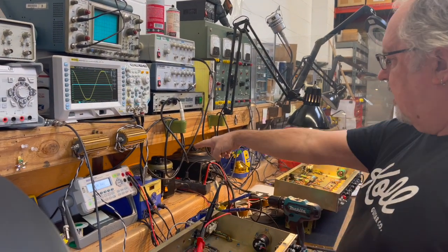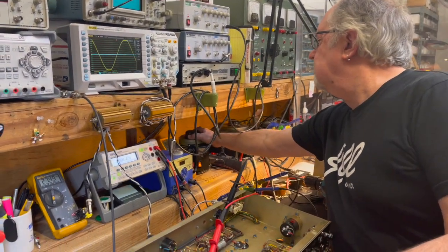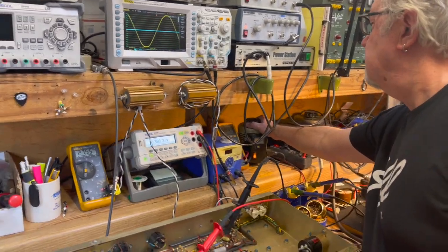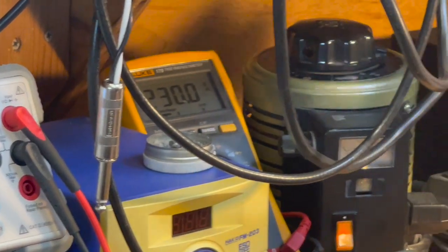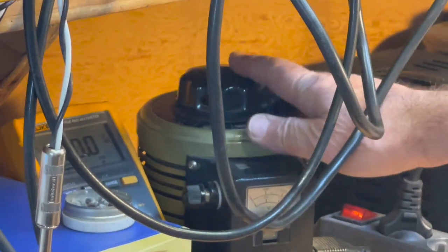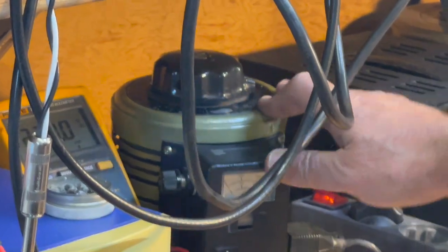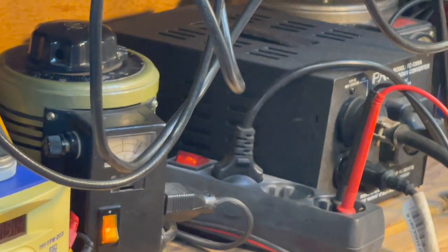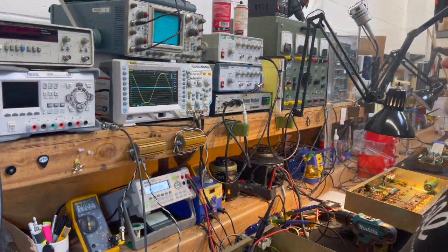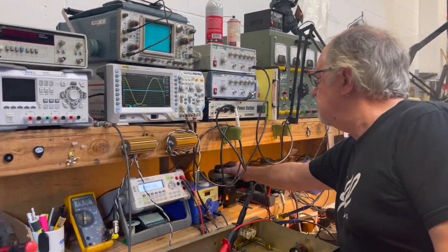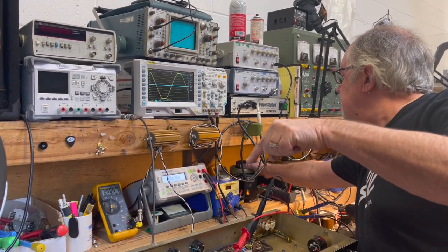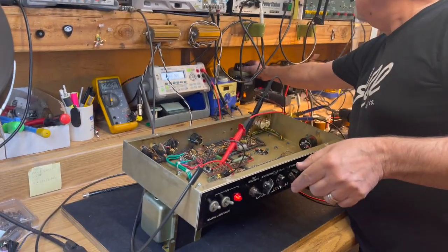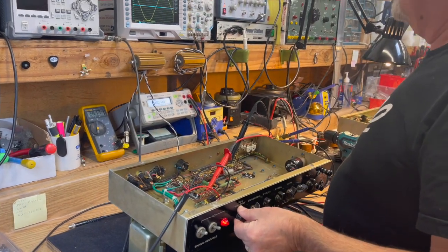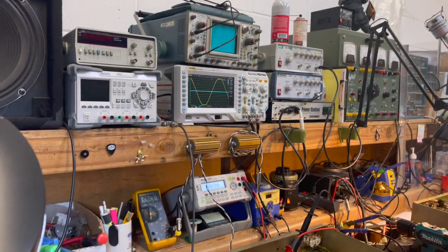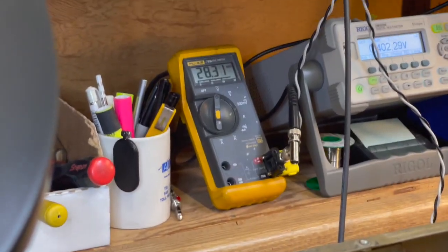We also lost about 3 volts of supply because I've got a step down transformer that I use for European voltage, and a variac here, so there's a little bit of voltage drop across there. So when you start pulling current through it, the voltage drops through all my test equipment. So we compensate for that by jacking the voltage back up to 230, so that it's 115 for this guy. I'm just going to go to 231, and then we'll hit that clipping, and we'll be at 28, which is 100 watts right on the nose. That's where we want to be.